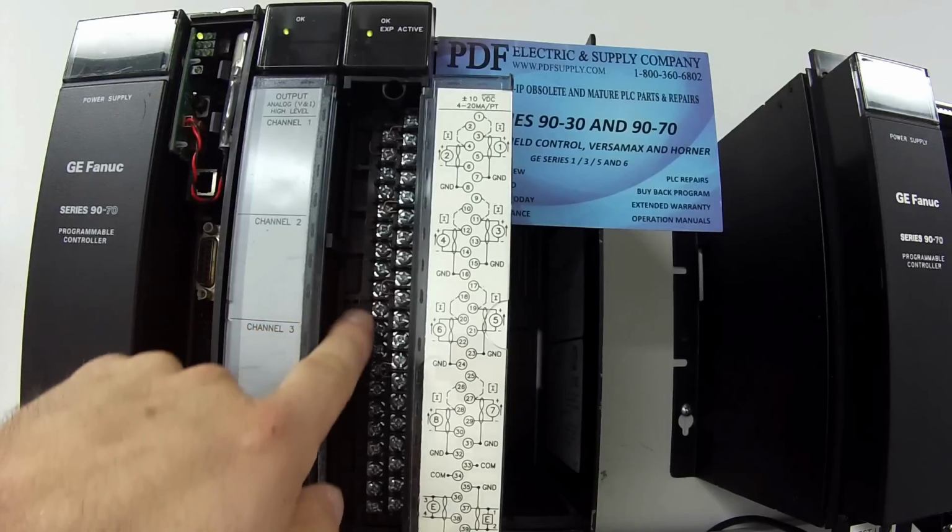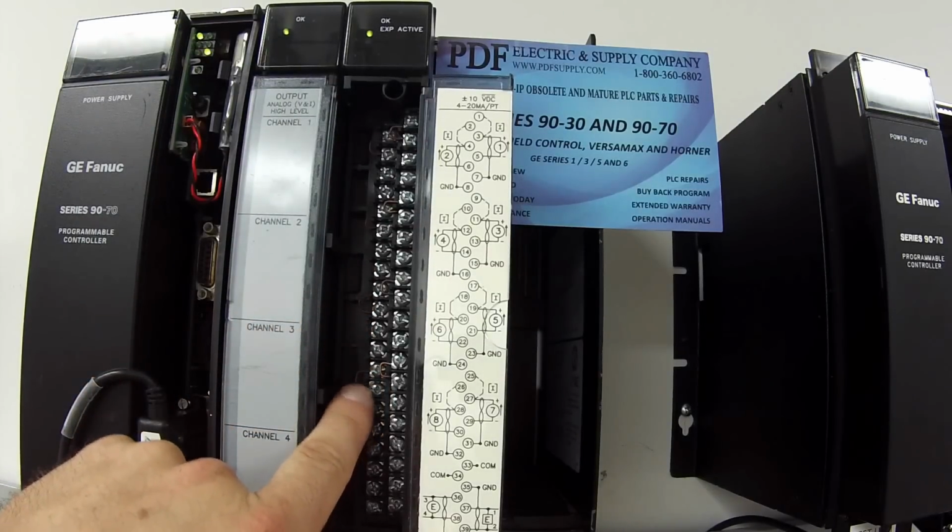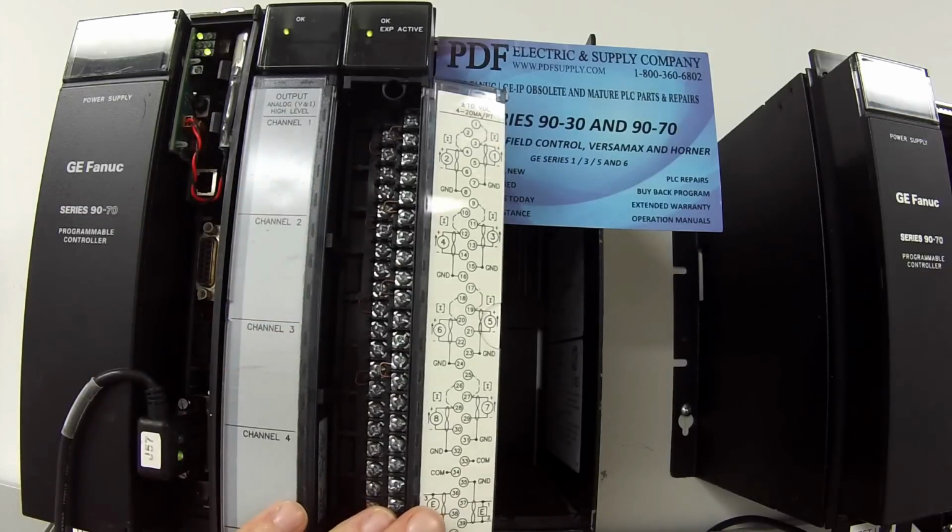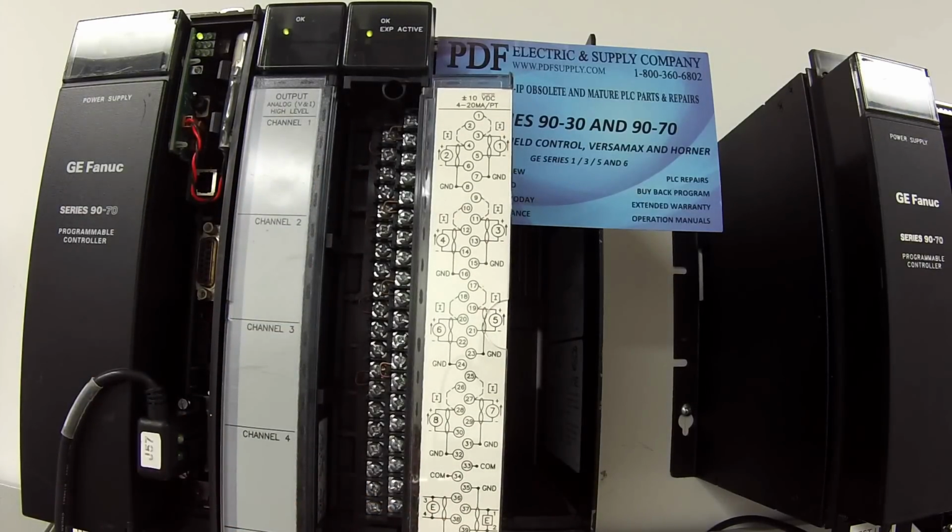And you can see that here. I have these copper wires that have been bent and put in place as a jumper, and you won't get a value or a reading on milliamp without that. So just please keep that in mind. I'm going to go to channel 1. And under range, I'm going to switch it to 4 to 20 milliamp, and that goes for all channels.